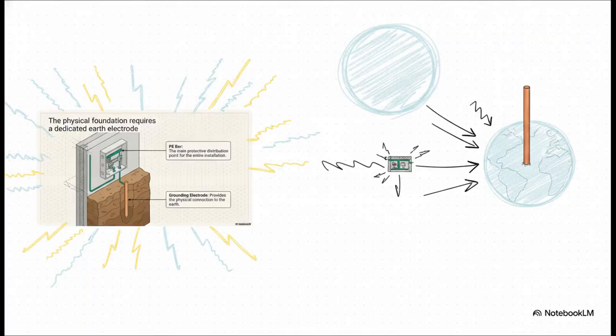All right, our physical build starts right now. You absolutely cannot just rely on the inverter itself for grounding. You need a rock-solid physical connection to the actual earth. We're talking about a copper earth rod driven deep into the soil. From there, a green grounding conductor needs to run straight up and directly into the main protective earth, or PE, bar inside your distribution box. That bar becomes your absolute safety hub.